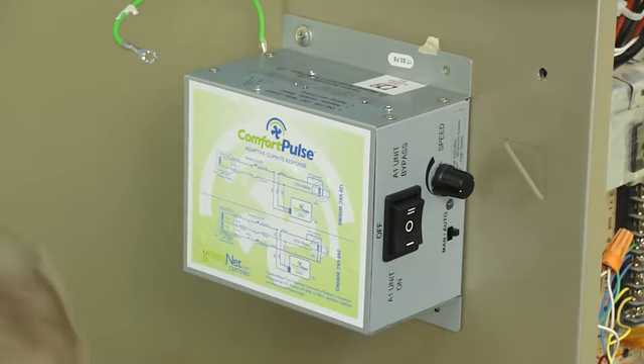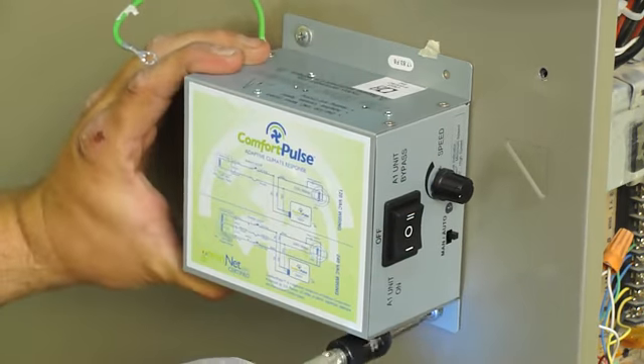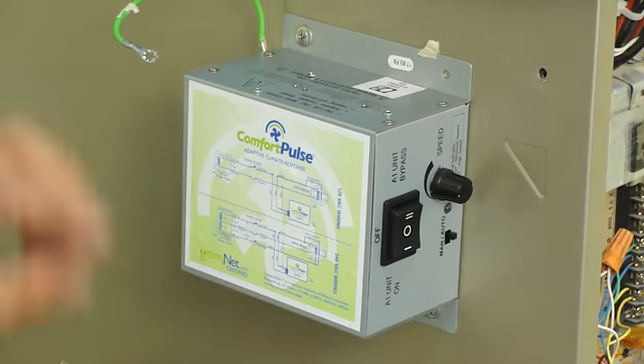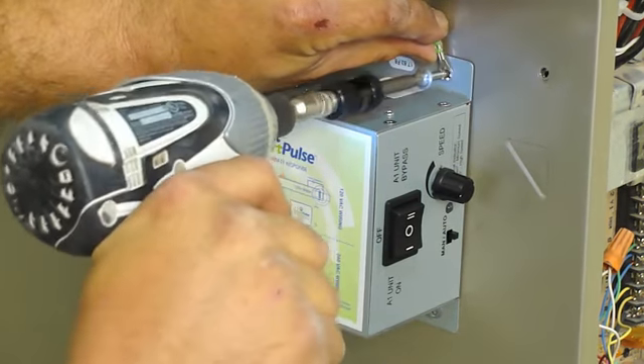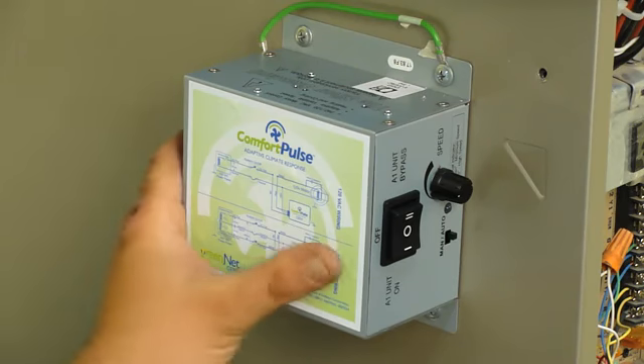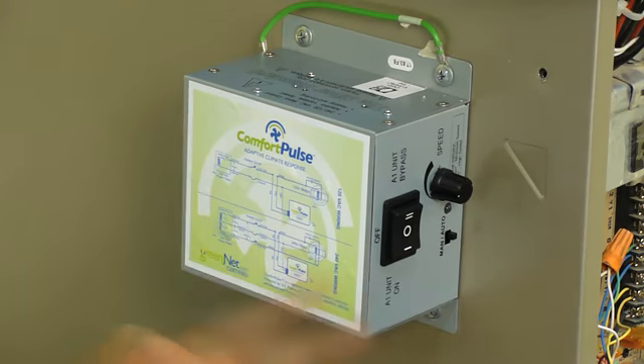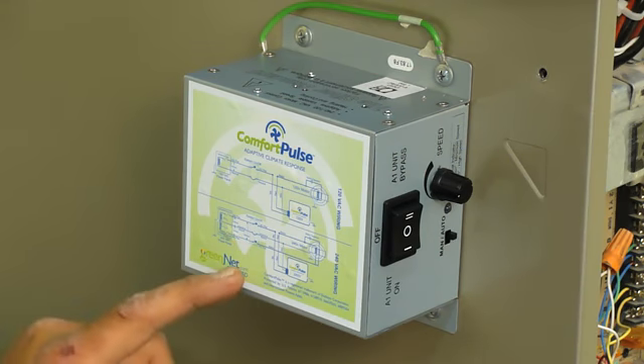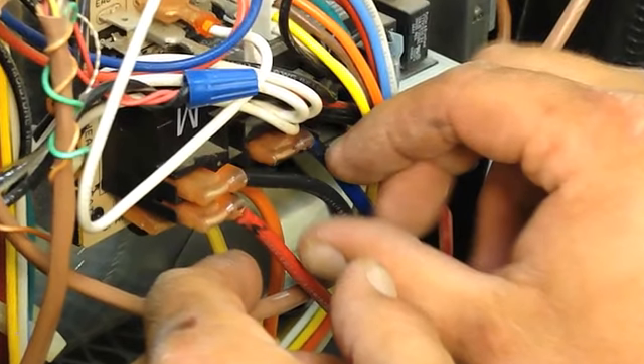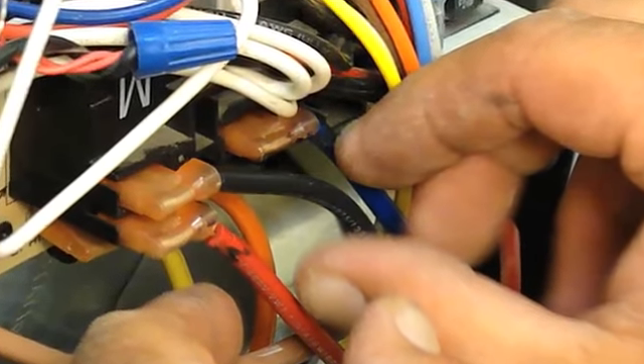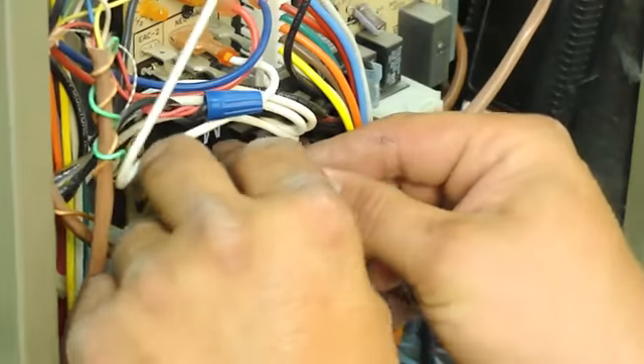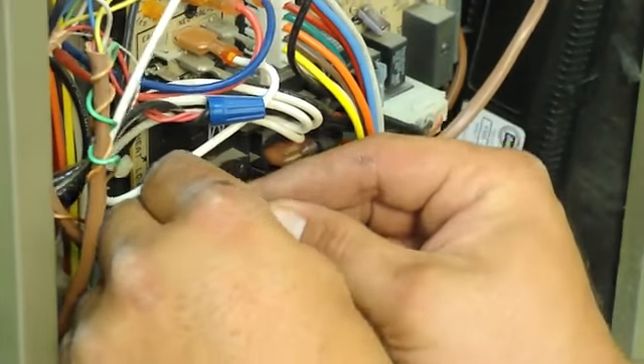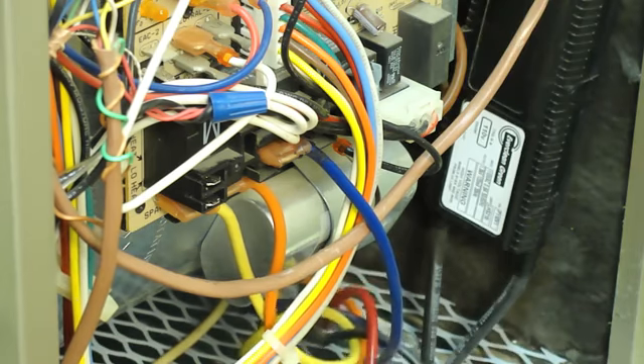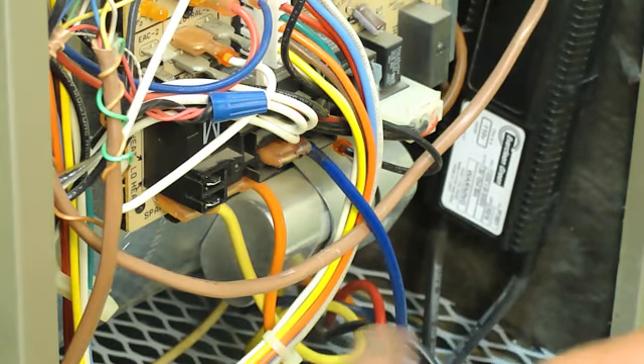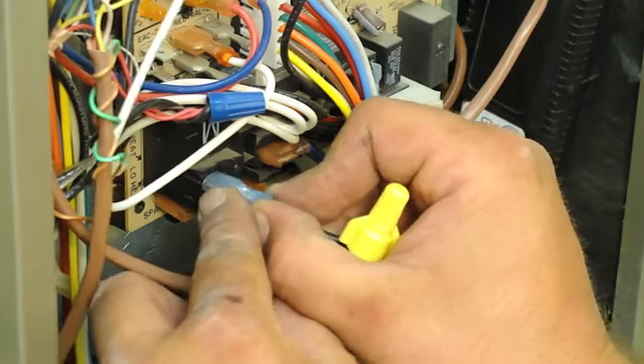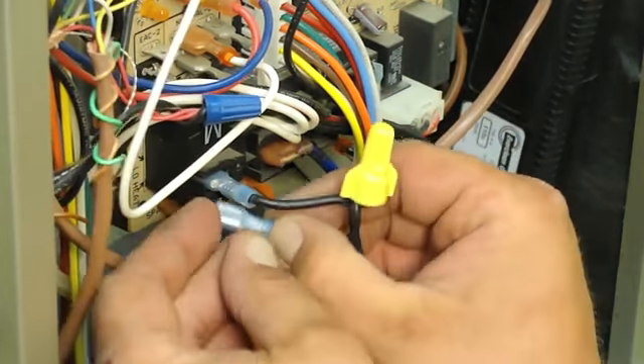First, choose a safe and secure location to mount the Comfort Pulse. While mounting the Comfort Pulse, attach the Comfort Pulse's green ground wire to the air handler unit frame. Next, refer to the schematic on the Comfort Pulse as a visual guide prior to connecting any of the wires to the HVAC unit itself. Connect the Comfort Pulse cable black wire to the line side of the fan input power. For units that utilize low speed for heat and high speed for cool, remove the low and high speed tap motor wires and connect the Comfort Pulse to those inputs. Keep in mind there is usually only one wire, the high speed tap, for a heat pump.